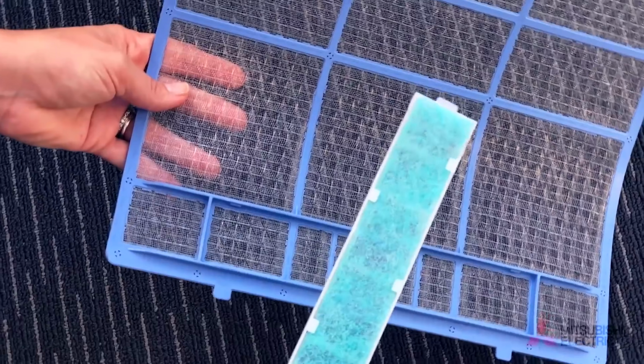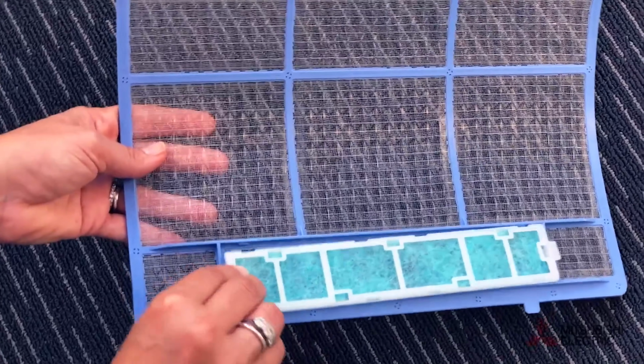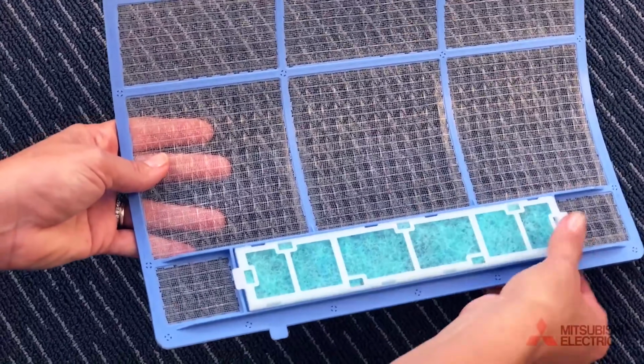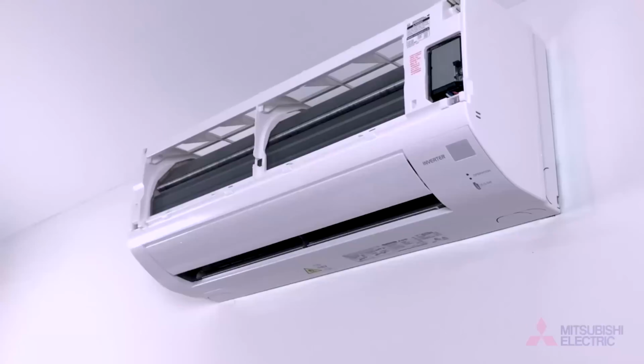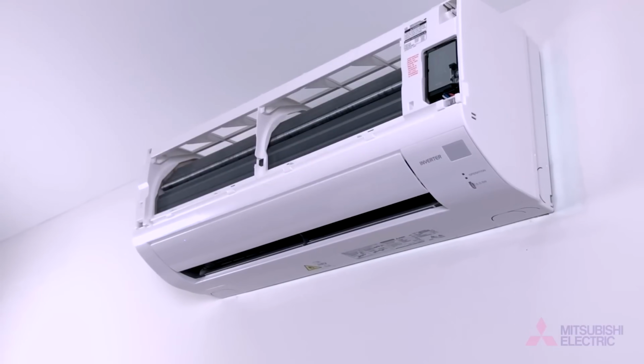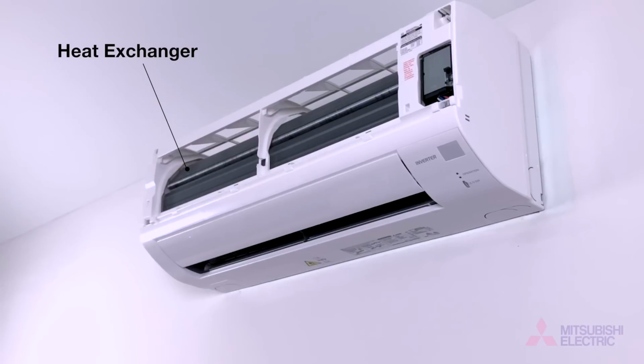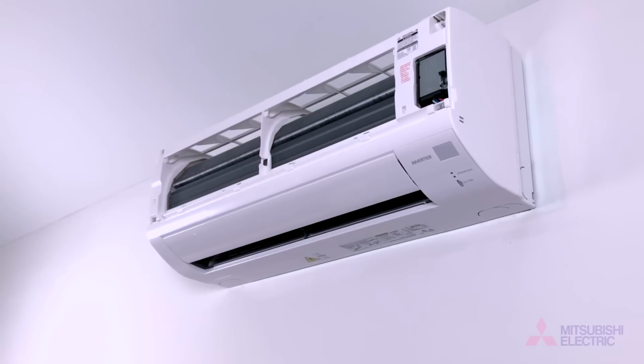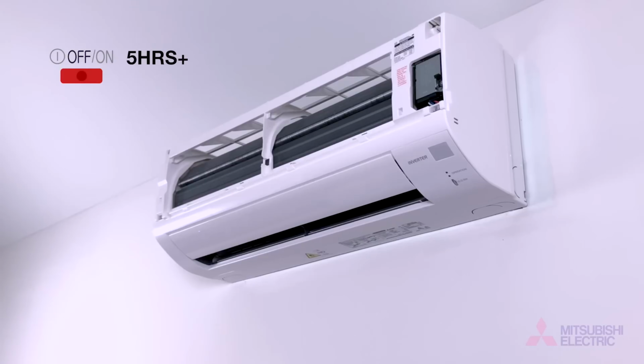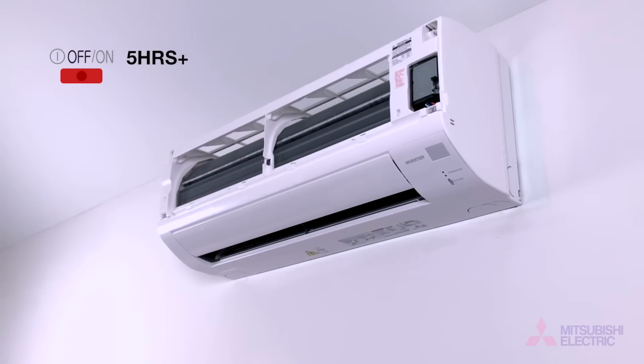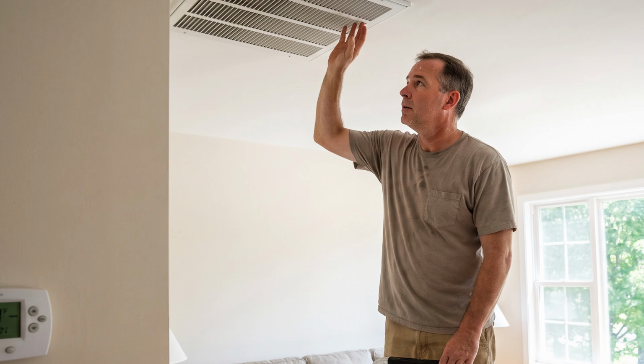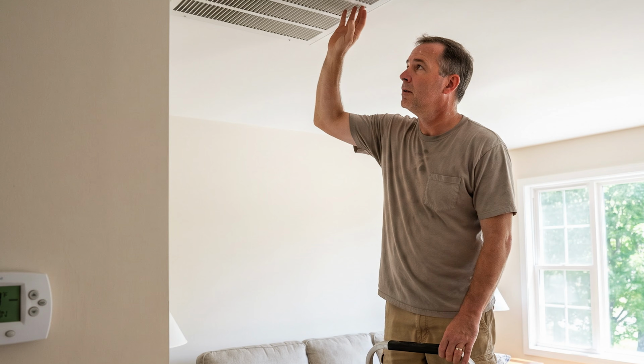Filters are rated on a scale called MERV. The higher the MERV rating, the tighter the weave of the filter material. When you buy a filter with a very high rating, the material is so dense that it restricts the amount of air the system can pull in. Think about trying to breathe through a heavy winter blanket. That's what you're doing to your blower motor. Your air conditioner needs a specific massive volume of airflow to work properly.